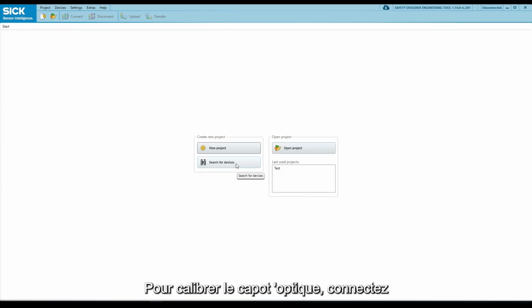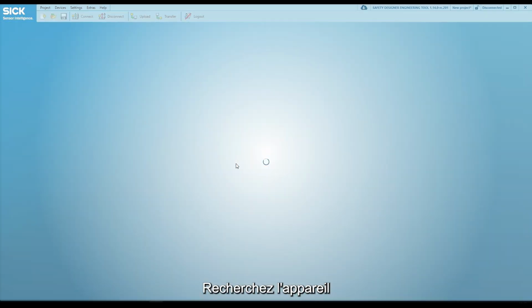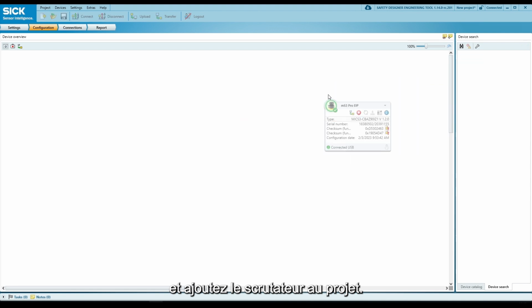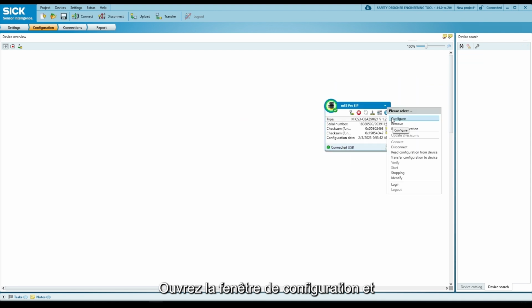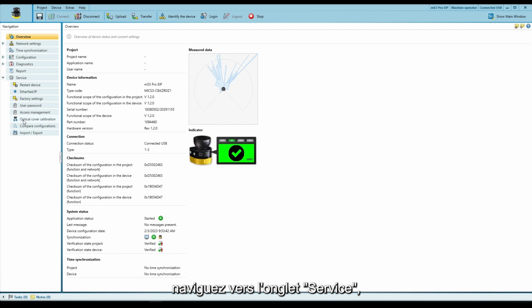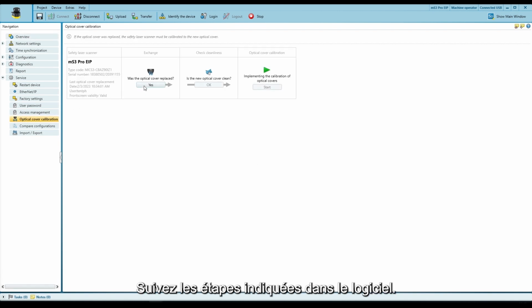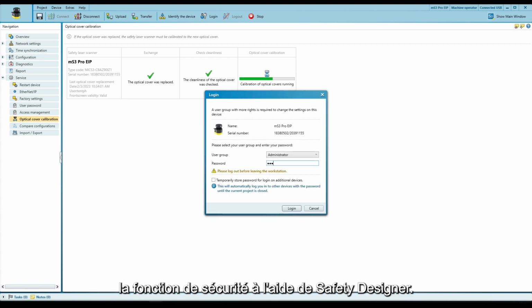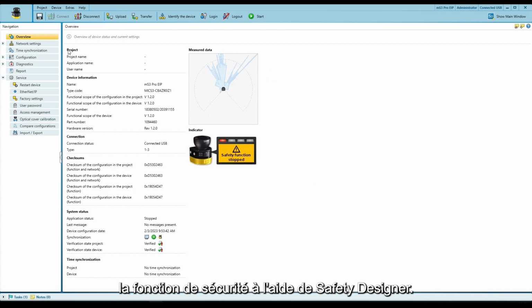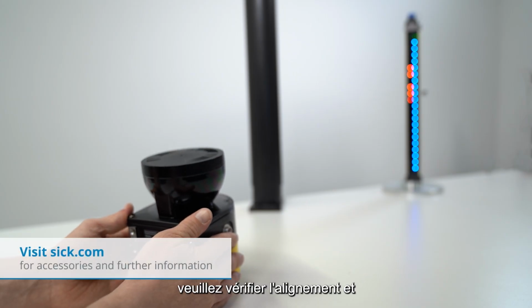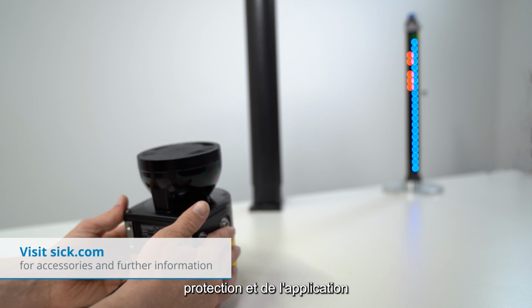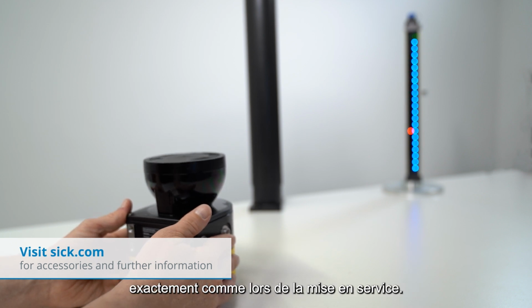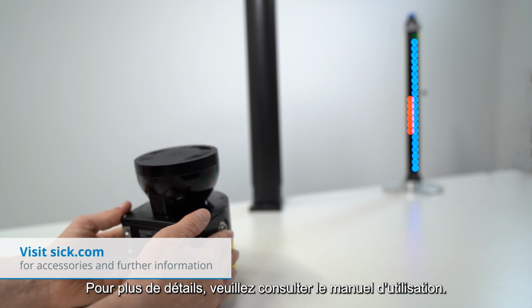To calibrate the optics cover, connect the device to a power supply and the Safety Designer. Scan for the device and add the scanner to the project. Open the configuration window and navigate to tab Service and then Screen Calibration. Follow the steps shown in the software. Afterwards, start the safety function using Safety Designer. Before restarting the application, please check the alignment and effectiveness of the protective device in the application exactly as during commissioning. For more details, please see the user manual.